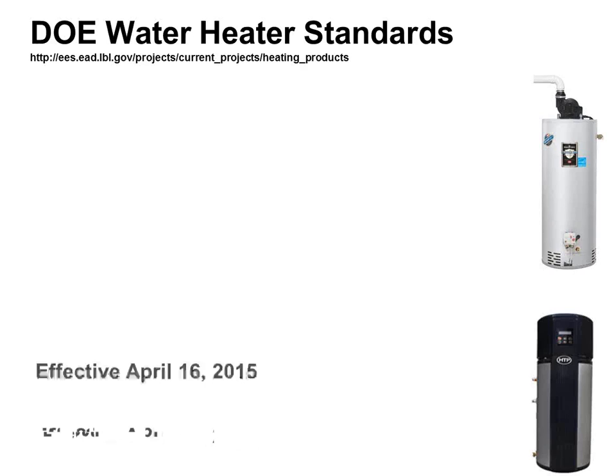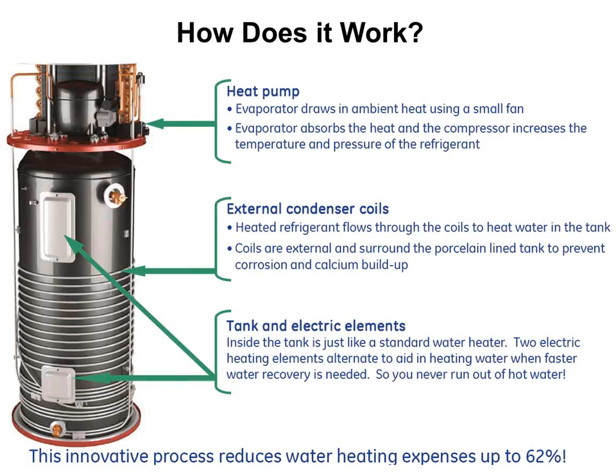In the wintertime, it's a bit of a heating penalty. I don't know if it's enough to even change your load calc on a building or a house, but it's a little bit of a heating penalty from stealing that air. In the summertime, it's a bit of a credit because I'm actually dehumidifying that air, right, which helps me do a little bit less cooling work with my latent side of my cooling system.